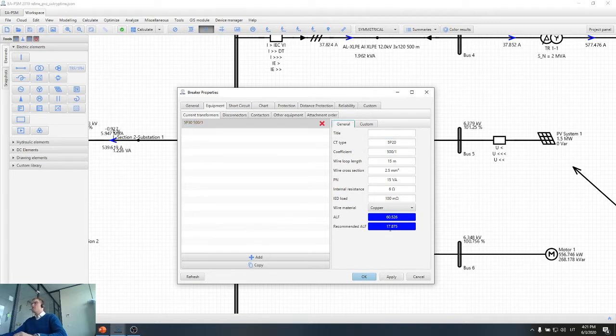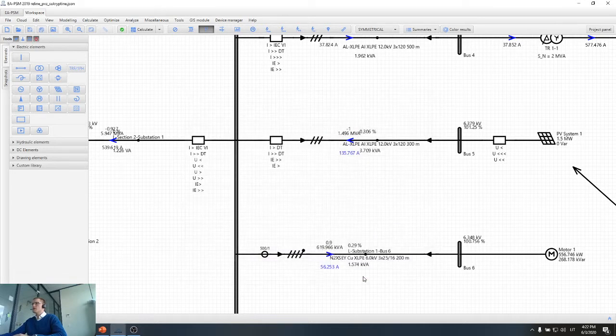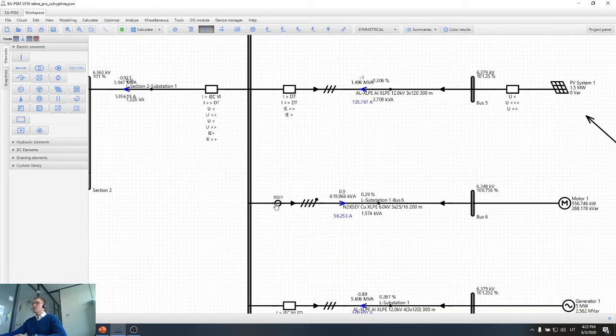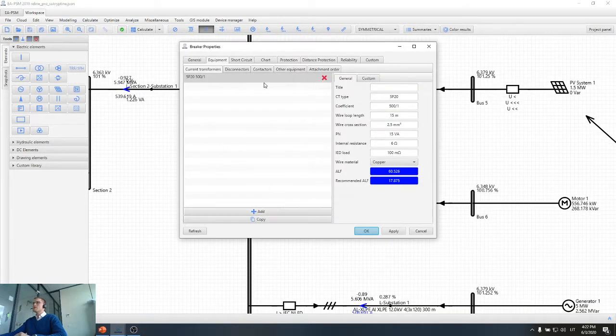So accuracy limiting factor is a very important parameter because it allows to select transformer with good enough rating to avoid faulty readings of the current. So if accuracy limiting factor is too small, during short circuit operation, transformer will saturate and will provide currents that are not very exact. And this might be a problem for some of the protection devices. Therefore 17 would be a good value to set. So now I have a current transformer selected.